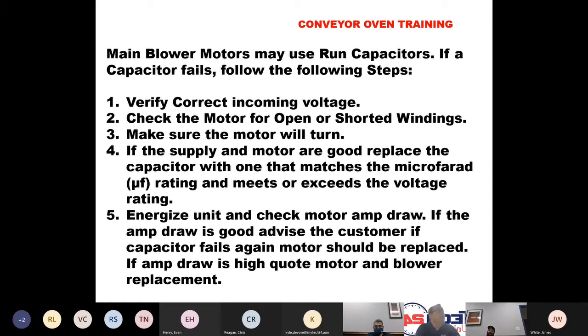If all of these things are correct, go ahead and replace the capacitor with one that matches the microfarad rating exactly and meets or exceeds the voltage rating. So your microfarads on run capacitors have to be exact. Your voltage rating can be the same as the one you have or higher, but you cannot go down in voltage rating.